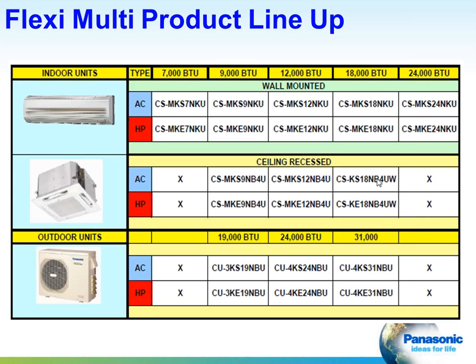There are also multi-zone systems in larger tonnage capacities in 1.5 ton, 2 ton, and 2.5 ton. Focusing on the outdoor units, that lower column, the model numbers that you see there are CU-3, CU-4, and again CU-4 for the 1.5, 2 ton, and 2.5 ton systems respectively. The 3 tells you that there's 3 ports on that 1.5 ton unit and 4 ports on the 2 ton and the 2.5 ton unit.